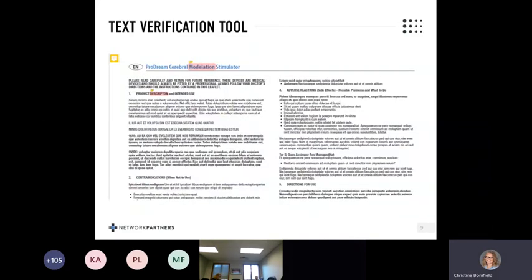At this point, your graphic artist has revised your initial test IFU. Whether he's just tidied up a multi-language IFU or completely reformatted a multi-language IFU into 24 separate single-language IFUs, you need to confirm that the only content adjustments were part of the change order. You can conduct a 1-over-1 visual review comparison of the original and the revision. But reformatting every IFU, every language, can so easily lead to an unintended change.